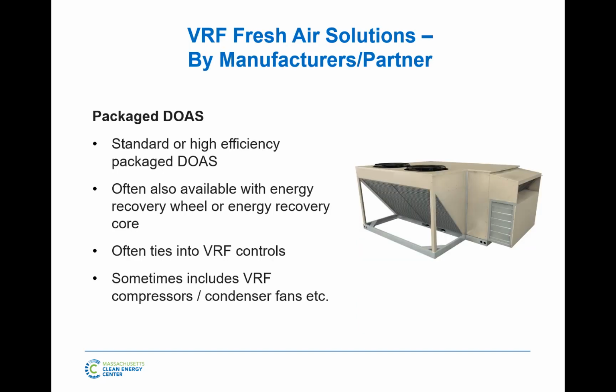This is the packaged version of it. Again, to the naked eye, even more, this looks like a typical packaged DOAS unit that can do fresh air into your building. But the compressors in there are VRF compressors, VRF condenser fans. Doesn't have to be. It could be a regular unit, but it needs to be a DOAS unit. So you'll see that. Very typical. You look at a roof of a building, VRF, you've got 10 VRF machines and one of those.